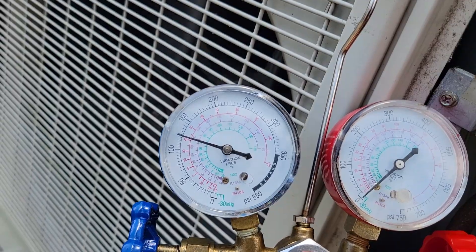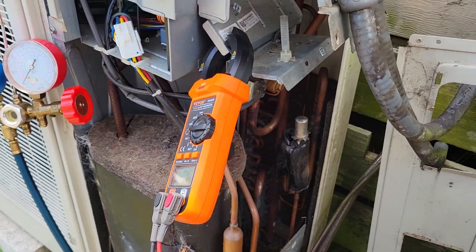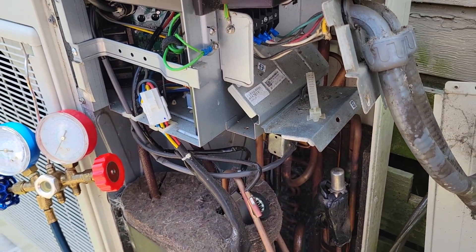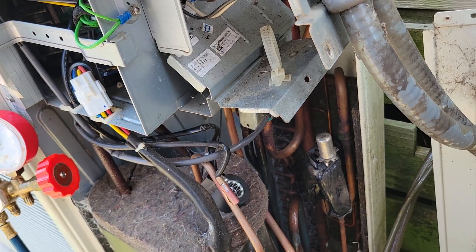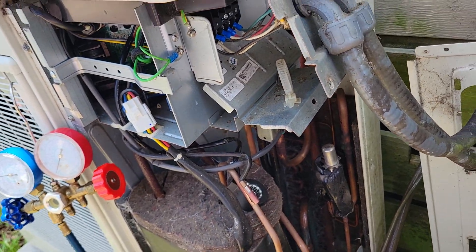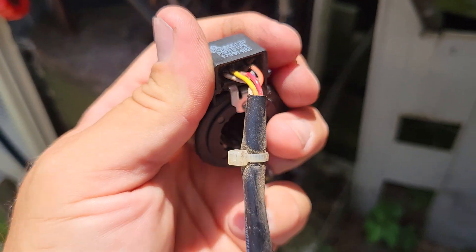And that's looking pretty good to me. So there you go — just wanted to share that with y'all, save you $300 on a magnet. Also, just in case anybody's wondering, the part number is a little hard to find. This is for a Daikin 6-wire — there are Daikin 5-wire versions too, but mine has 6 wires.